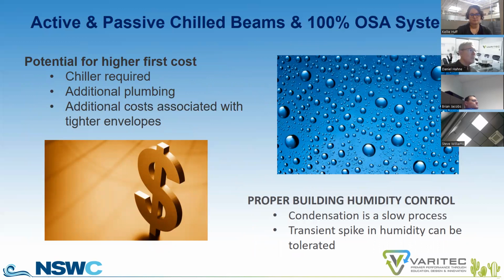The potential drawbacks of chill beam systems are many contractors are unaware of the system, haven't installed them. The first cost estimates are such that they can offer a first cost premium. Also, you have additional plumbing associated with it. And another thing to consider is the additional cost of a tighter envelope. You need to make sure that the perimeter wall has a vapor barrier or certainly a good air barrier configuration so that you reduce the humidity infiltration on a monsoon day, high humidity condition, because humidity will always go from wet to dry, and building pressurization will not stop humidity infiltration from the outdoors to indoors. So you need to be aware of a tighter envelope to assist in controlling humidity to the space.